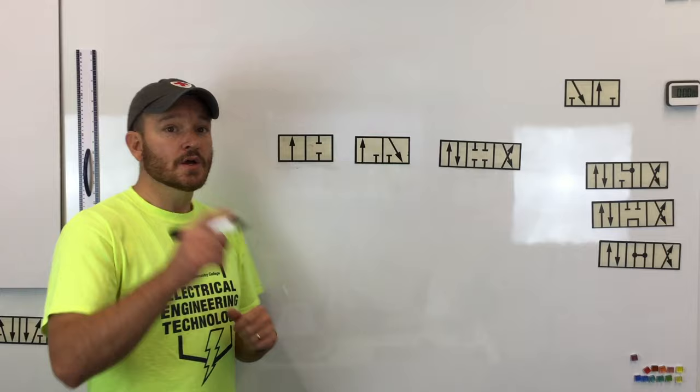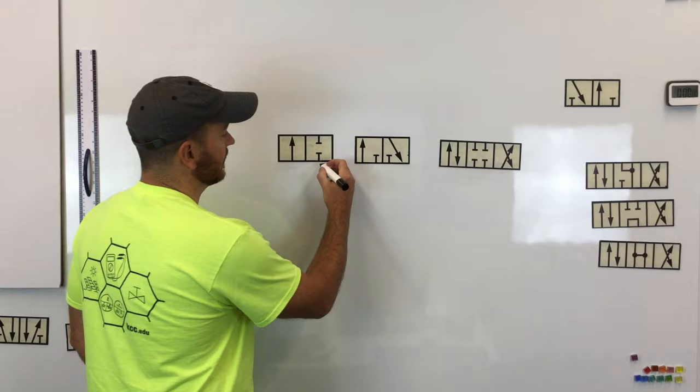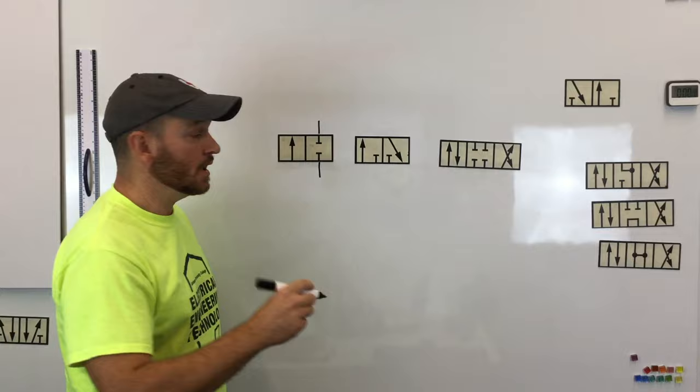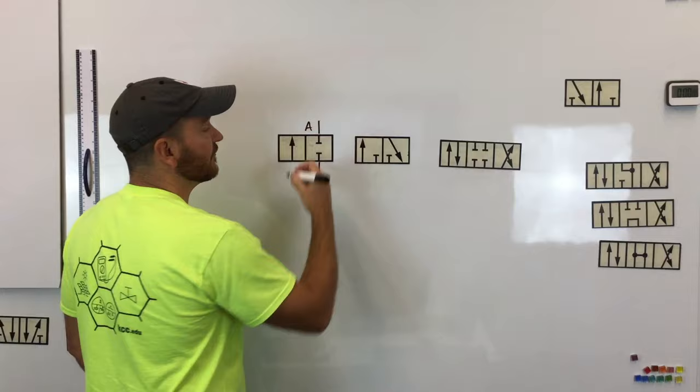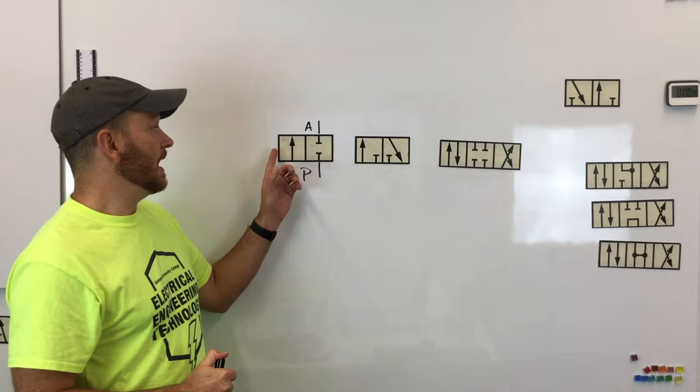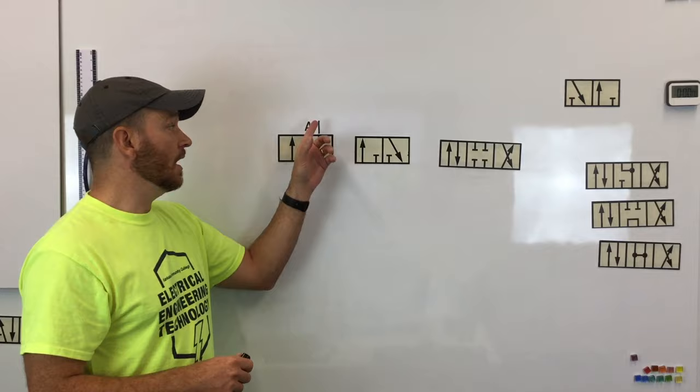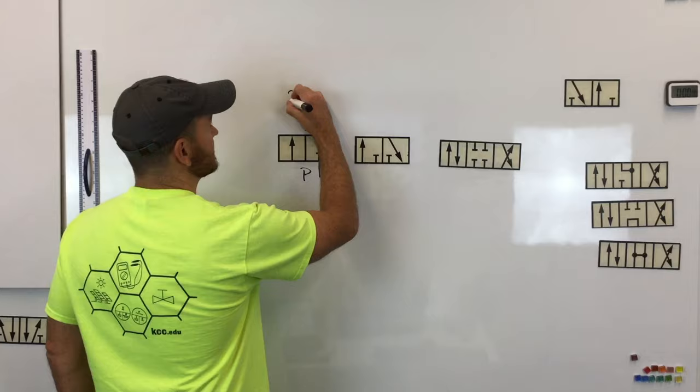The first one we want to look at is the two-position directional control valve, and this one has two ports on it. The P is the pressure port, and on the top is A for the actuator port. This would be considered a two-way, two-position directional control valve — most commonly identified as a two-two directional control valve.